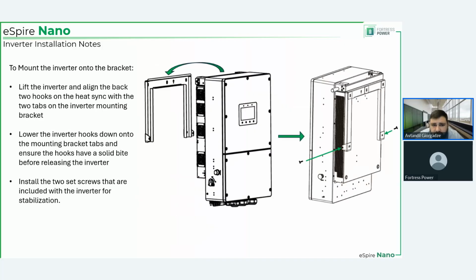Mounting the inverter onto the bracket. We presume that the bracket is on the wall, following all the requirements that we were outlining before. Then it has almost a kind of lip, and the inverter is hung on top of that lip, just like you see right here. Then, so that the lip doesn't become the axis of rotation, you put in two screws in the bottom of the bracket, one on each side, and voila, the inverter is secured in its place.